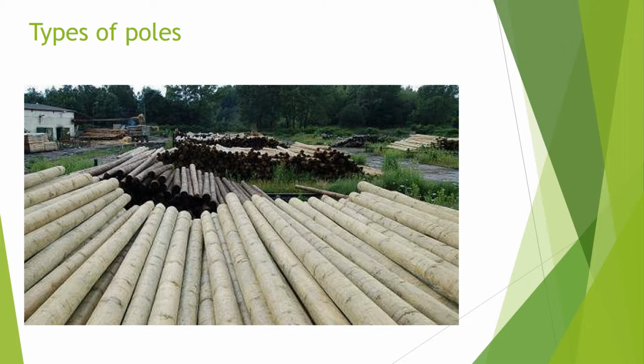Types of poles. Firstly, let us look at the wood poles used in overhead line construction. These will be used to carry conductors carrying voltages ranging from 230 to 400 volts in LV networks up to and including 11,000 volts, 33,000 volts, and in some areas 132,000 volts. They are produced from the trunks of evergreen trees grown within the UK or imported from abroad. They are treated with a preserving agent such as creosote. A treated red fir pole can be expected to give 25 to 30 years service, but British fir or larch can last significantly less depending on location.